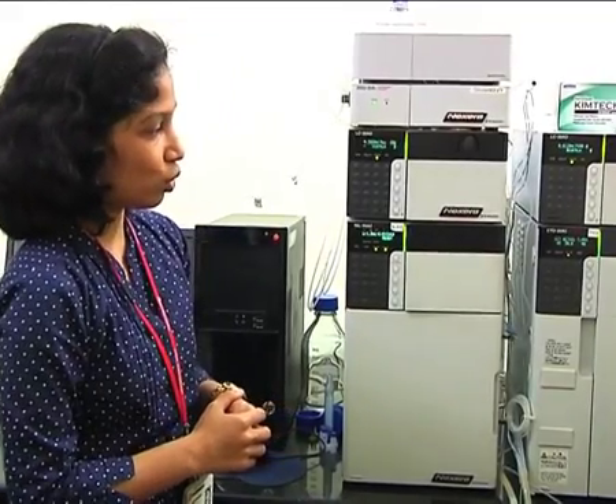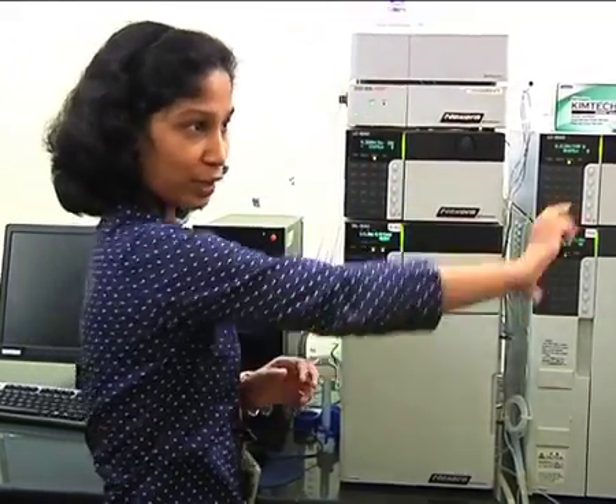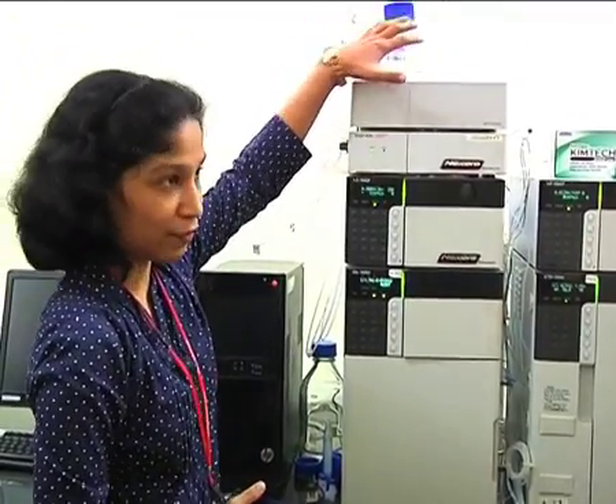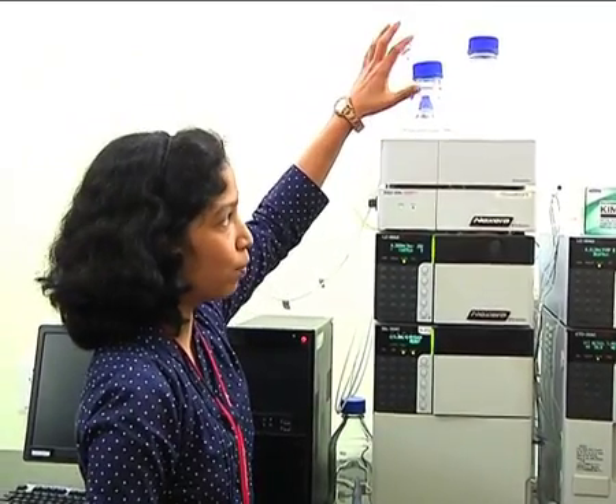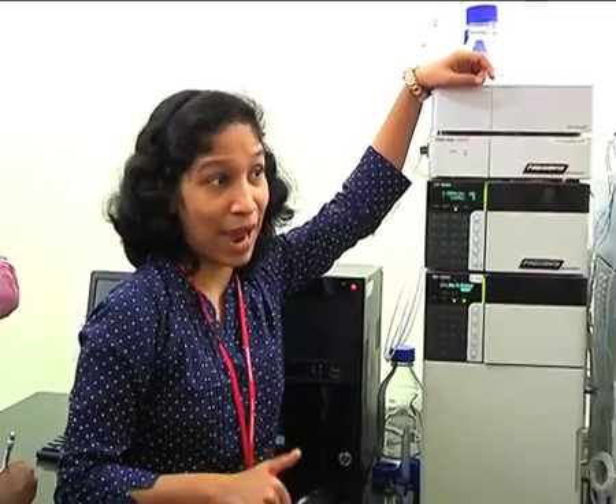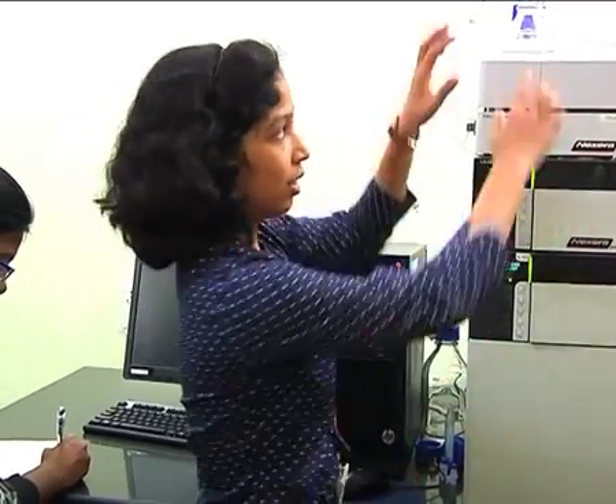First, I'll explain the flow path of the HPLC system. These are the mobile phase reservoirs, with port A and port B. There are two types of HPLC configurations available. One is called a high pressure binary gradient system, and the other is called a low pressure quaternary gradient system. High pressure binary gradient means if you have two mobile phase ports, then there will be two pumping units, one for each of the mobile phase ports. That becomes high pressure binary, and binary because there are two.